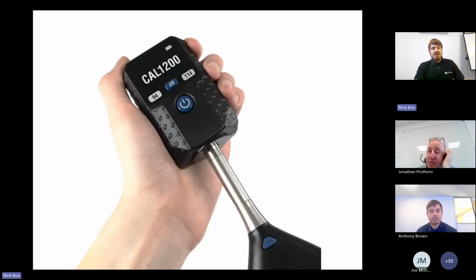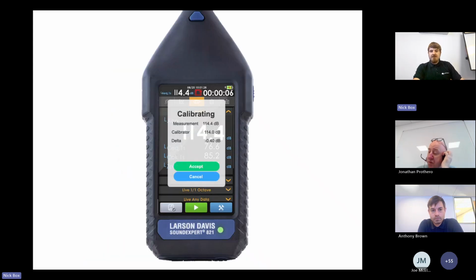One function that the Sound Expert has is an automatic calibration function. This is very easy - it's as simple as turning the calibrator on, putting the meter in the bottom, and sliding the microphone into the calibrator. Once you've done this, an automatic pop-up will come up on the screen. Once the calibrator is stabilized, you'll get an option to accept the reading, and once you press accept, the calibration is totally done.